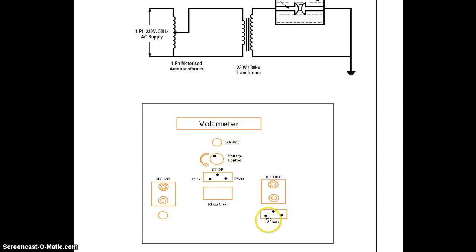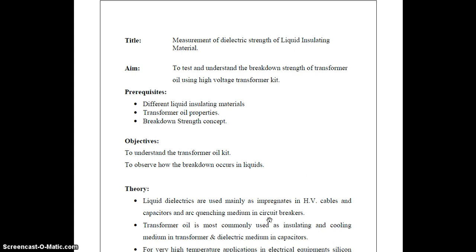The title is measurement of dielectric strength of liquid insulating material. The aim is to test and understand the breakdown strength of transformer oil using the high voltage transformer kit, in which different liquid insulating materials can be tested and transformer oil properties obtained. Then the breakdown strength concept. Objective: to understand the transformer oil kit and to observe how breakdown occurs in liquid.